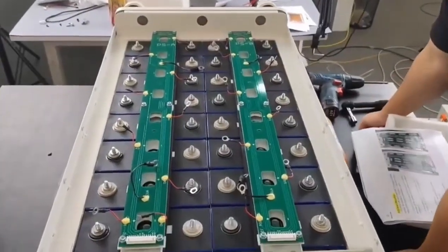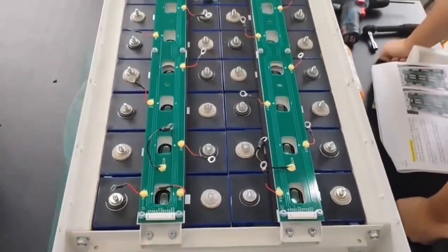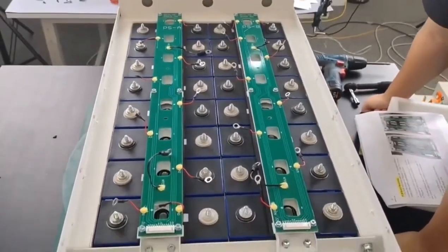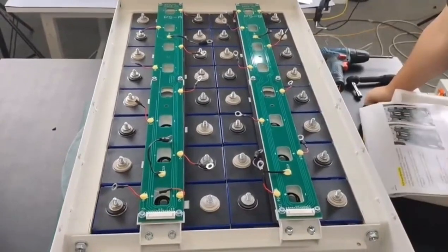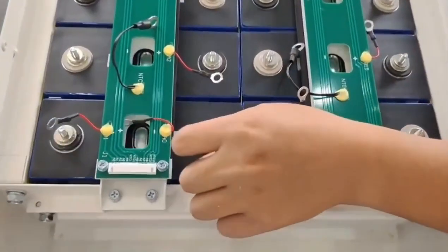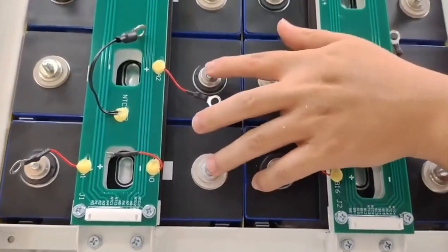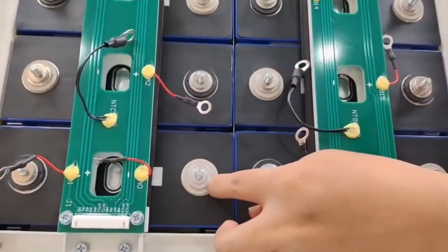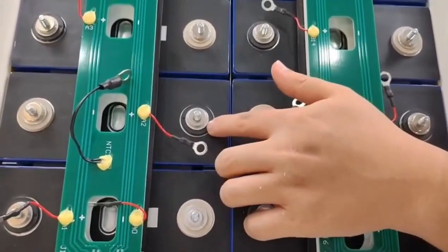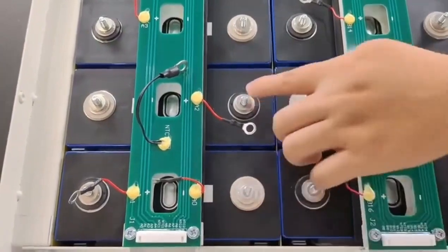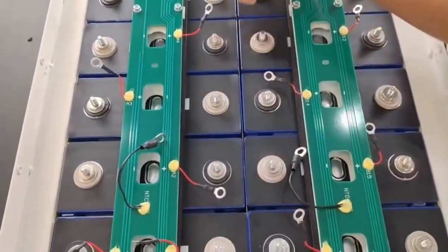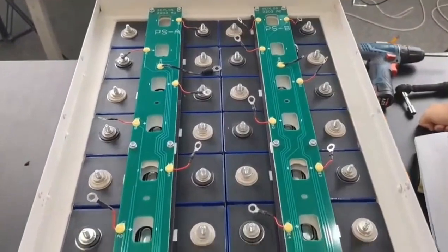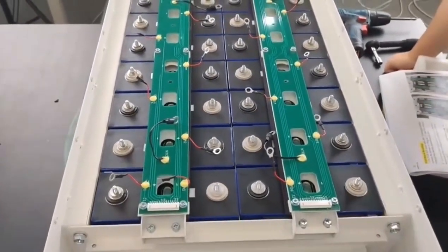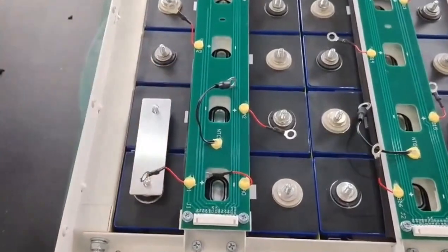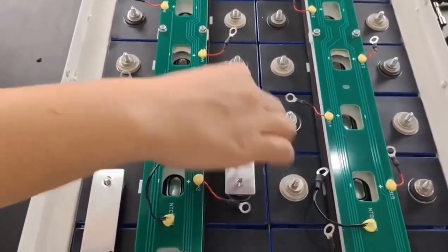The next step, we need to use the bus bar to connect the 16 cells. Before this, we must confirm the terminals of the cells one by one. Each one must be negative, and the next must be positive. Just like this one, we can check it, the white one and the black one. After we confirm this, we can put on the bus bar, one by one, the positive to the negative.